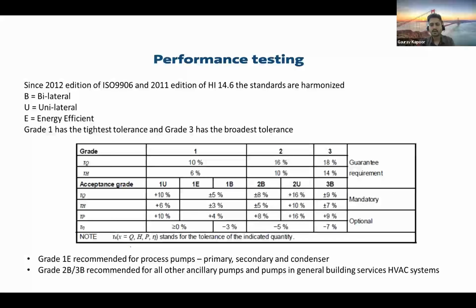So for centrifugal pumps, the performance testing means the flow, head, power and efficiency, which is given on the data sheet. When any manufacturer issues a data sheet which has flow, head, power and efficiency, and when you receive that pump, you need to cross reflect it by understanding whatever we have requested for, whatever has been finalized, whether we are getting that machine or not. It is tested through a standard known as ISO 9906 or HI 14.6. Please remember, the HI 14.6 2011 edition is the latest, and 9906 2012 is the latest edition.